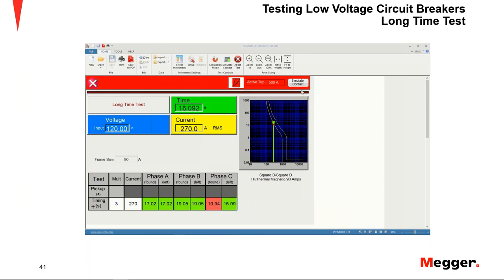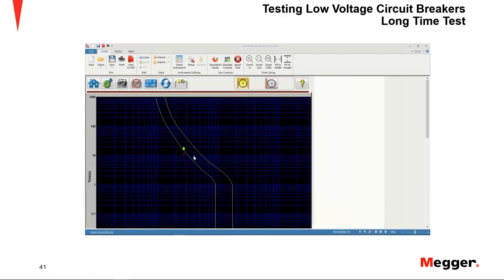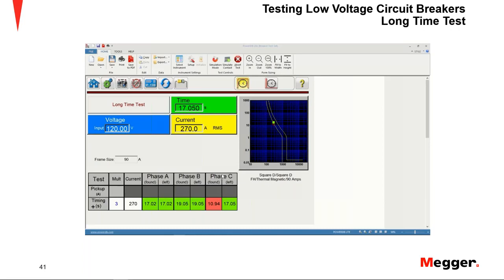So I'm going to do a retest on this case, phase C. So again, I don't erase my as found or my previous measurement. It's still in my report, but I can retest the phase if I did a change or some type of maintenance in the breaker. Okay. So that is the long time test. Let's go now to the instantaneous.